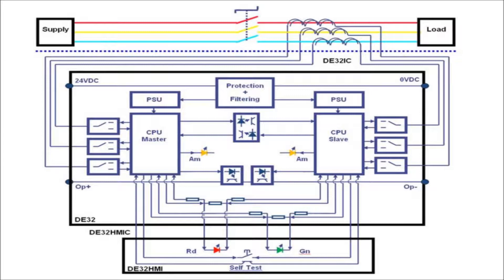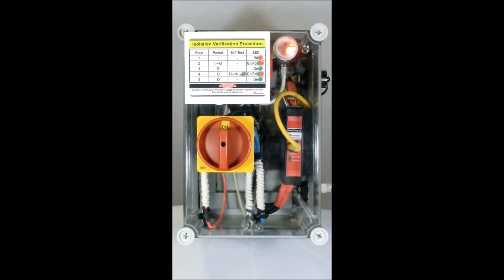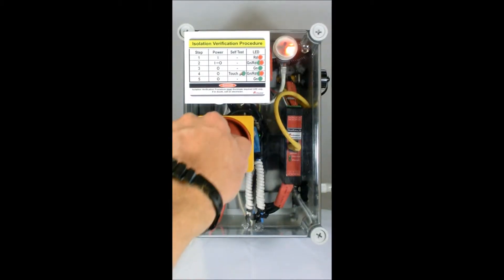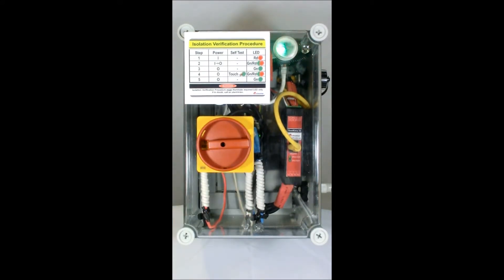Secondly, its functional safety design incorporates dual-channel architecture and regular self-testing. Self, or proof testing, is performed automatically on power-up, every red to green LED transition, and periodically during green LED indication.